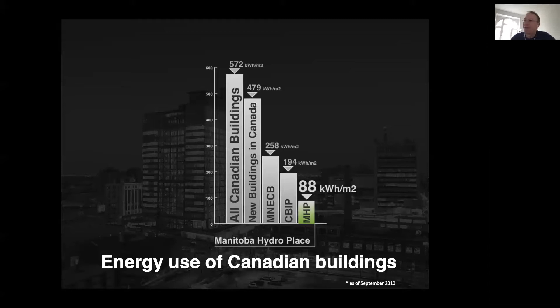Then we started to operate the building, and first of all, the good news: in terms of service calls for too hot and too cold, in the third year of operation, compared to the other buildings Manitoba Hydro operates, which are fully air conditioned, we have only half as many complaints for too hot and too cold. Which is quite a surprise, given the fact that with the radiant system we have no real control over the indoor environment. Since it's embedded in a 30 centimeter thick concrete slab, it reacts so slowly that if people complain that the space is too hot in summer, it takes 24 hours to reduce the temperature by about 1 degree. So there is no control over the space.